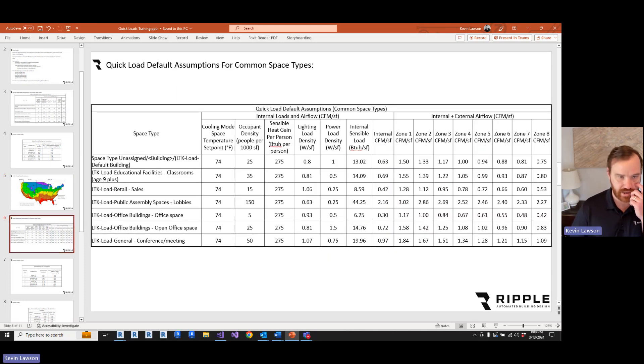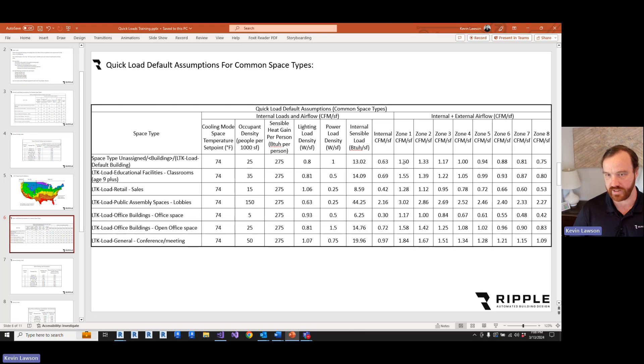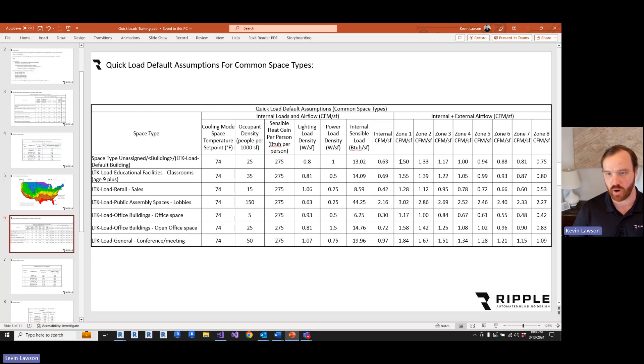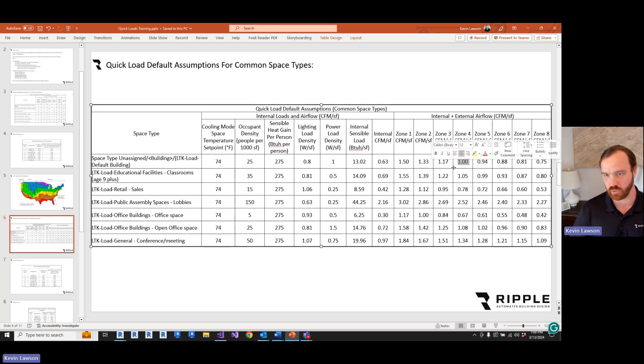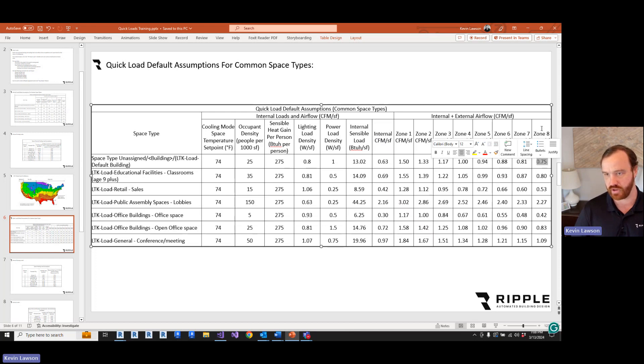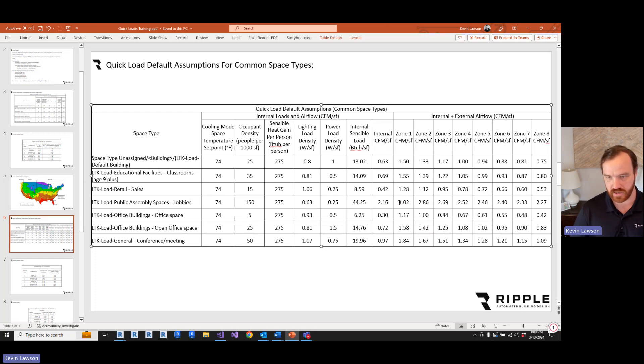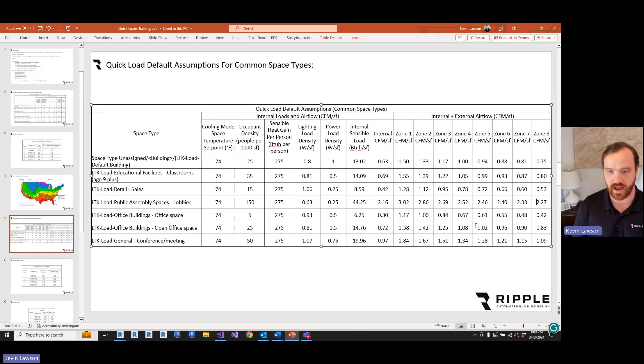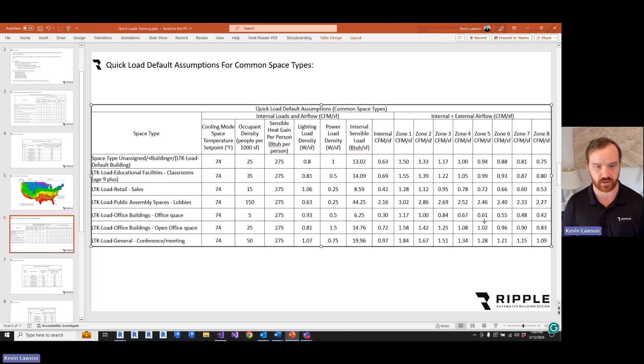Same space types here. We've got our internal loads here, and then we've got the addition of all of the different loads for each climate zone. So an unassigned default building is going to go from 1.5 CFM per square foot in Miami down to 1 CFM per square foot in Boston, down to 0.75 CFM per square foot in Alaska. And that's about what classrooms are. Assembly spaces, lobbies are going to go from 3 to 2.5 to 2.25. And that's what the default loads applied to the spaces are going to be.